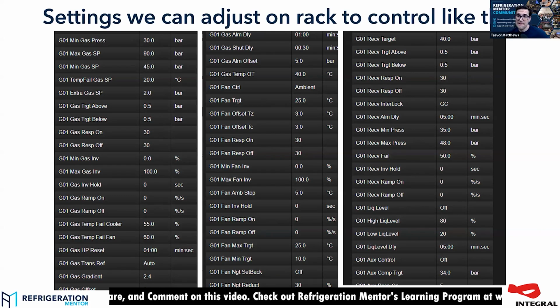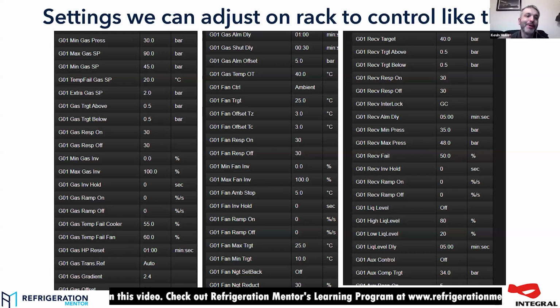So there are a lot of settings on an RDM controller you can adjust. As you can see, there's a probably scary number of settings to look at. But as I say, read the manual. For every parameter that's on there, the manual tells you what to do with it. The things I just wanted to point out: gas response in the first column is how fast the gas cooler valve works. I've got that set halfway up the scale. Same with the fans in the middle column, same with the receiver in the last column. And it just means that it can react reasonably quickly, but it's not panicking about things.